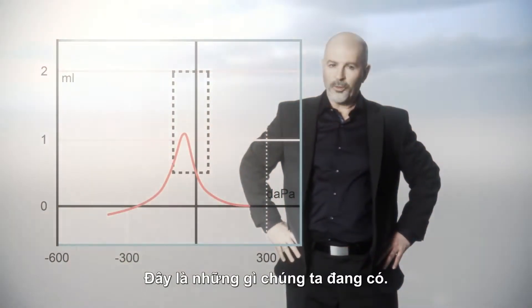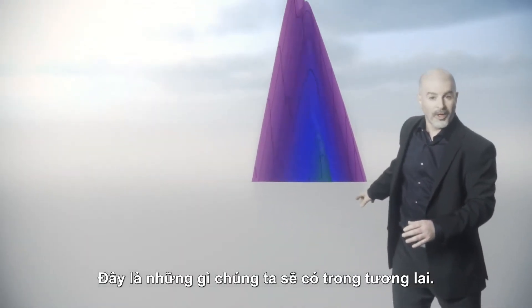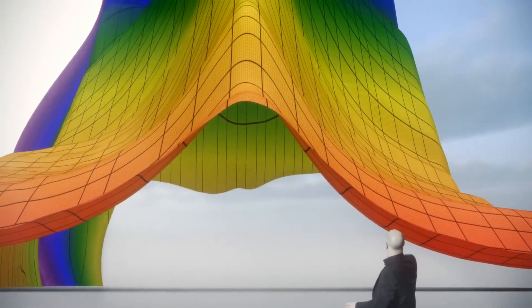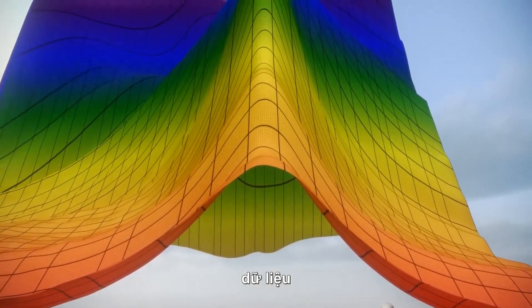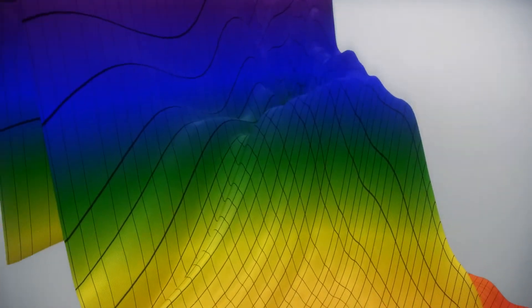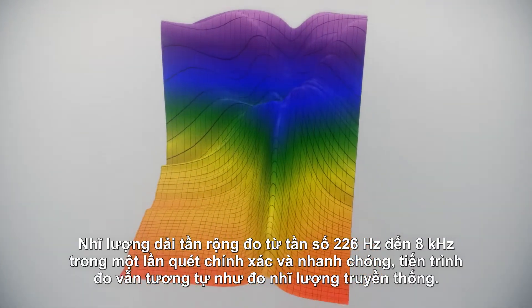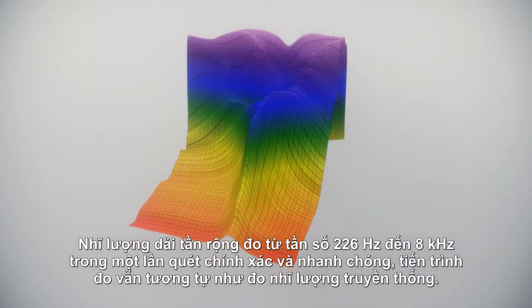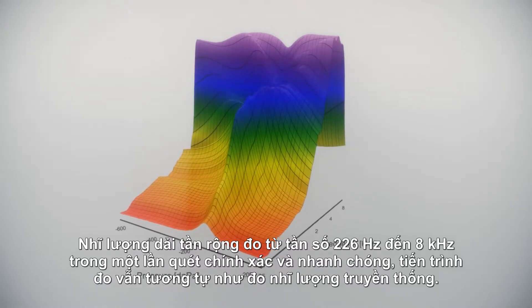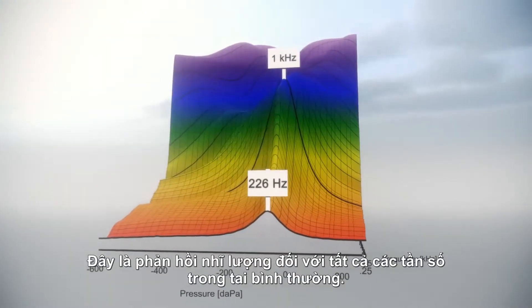This is what we work with today. This is what we will work with in the future — a mountain of data. Wideband tympanometry measures all tympanograms from 226 Hz to 8 kHz in a single fast pressure sweep, using the same procedure as classic tympanometry. Here, you see the tympanometric response to all frequencies in a normal ear.